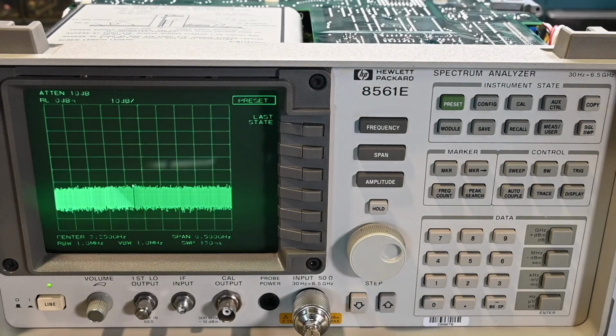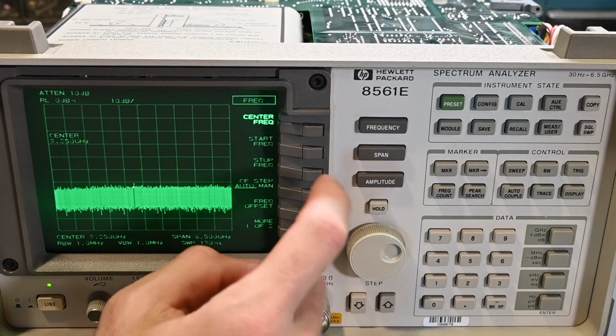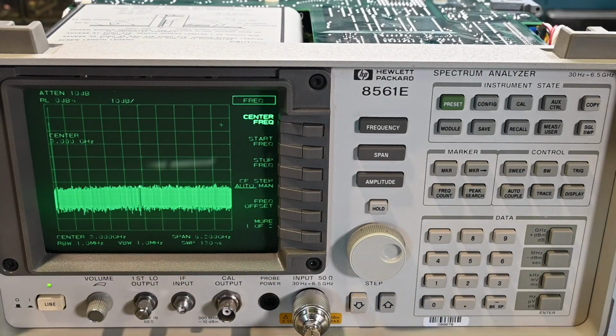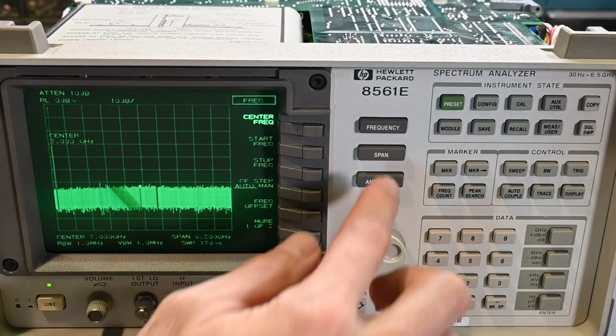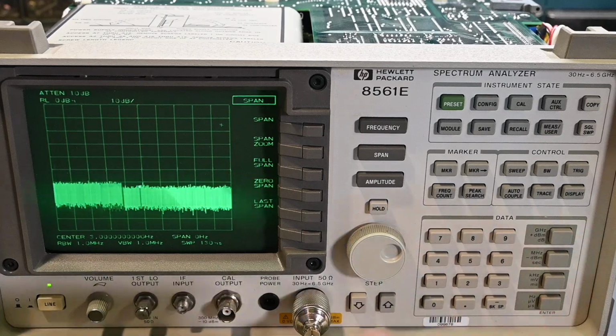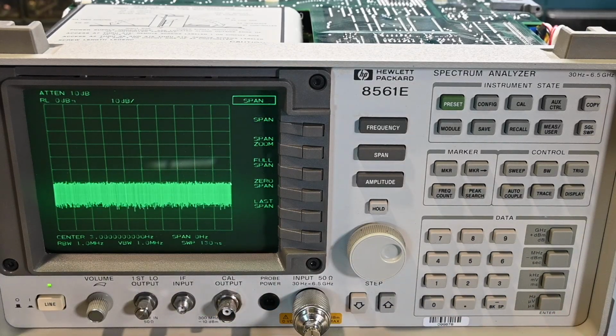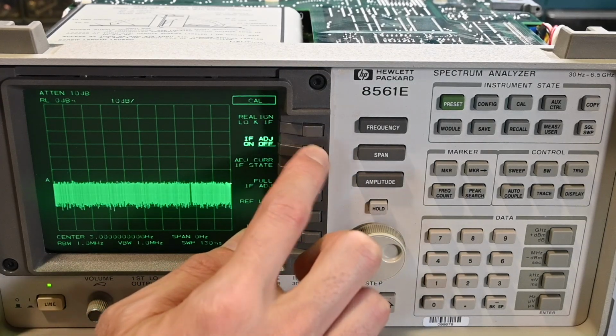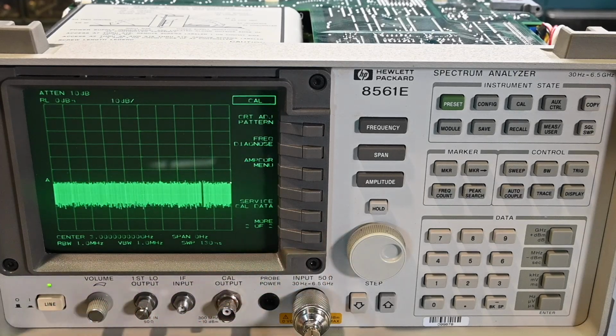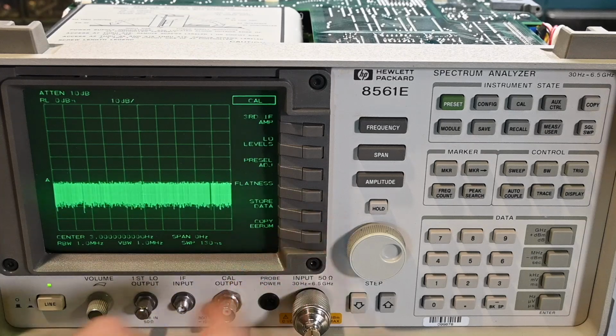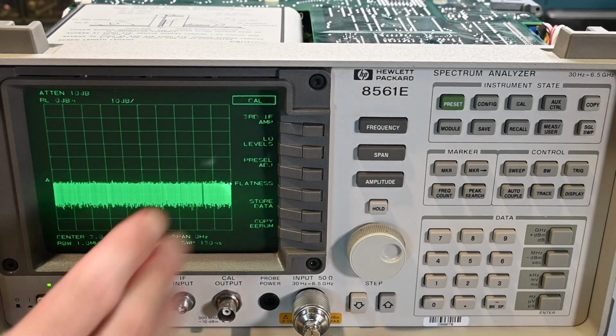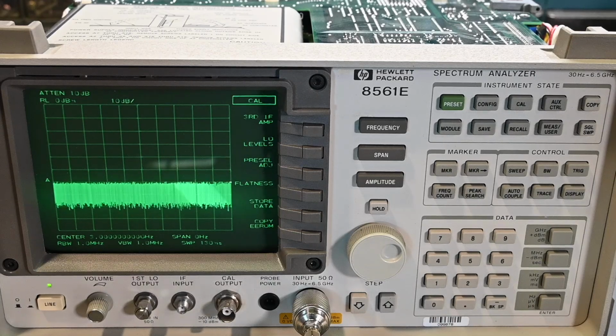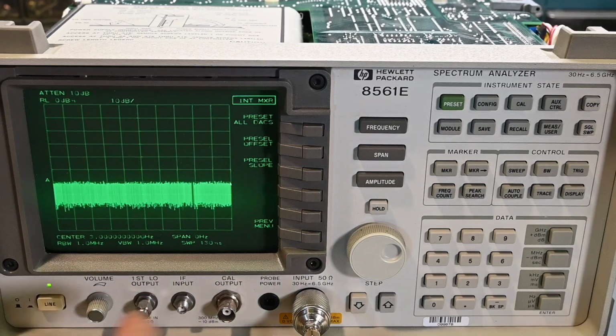So the next thing that we need to do is set the center frequency to 3 gigahertz. So go frequency and center frequency, it's there, 3 gigahertz, like so. And they want to do a span of 0 hertz, so span 0 hertz. Okay? And then it says what we need to do is press the cal button, so do that. And IF adjust offset. So I'm going to do that right here. Let's see, IF adjust there, off. More 1 of 2. Hit the service cal data, so that's right here. That service cal data comes up when that write protection jumper is moved over, otherwise that's not available in the menu. And then pre-select adjust. So pre-select adjust right here. And this is preset all DACs. So right here, preset all DACs.